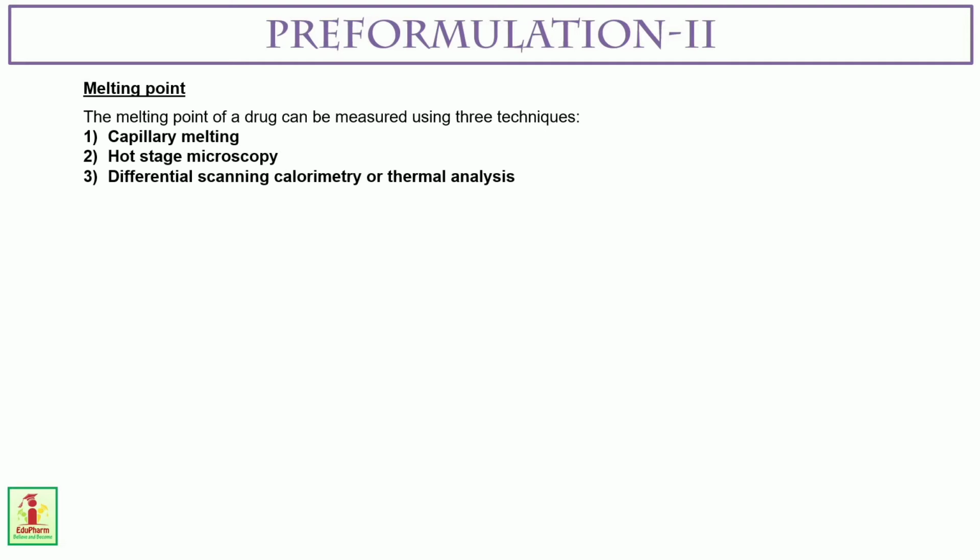In hot stage microscopy, it is the visual observation of melting under a microscope equipped with a heated and lagged sample stage. The heating rate is controllable and up to 3 transitions can be registered. It is more precise as the phase transitions can be registered on a recorder as the melting proceeds, and because of the high magnification, the values are more accurate.